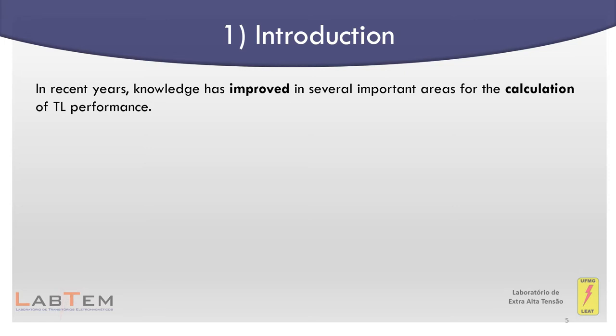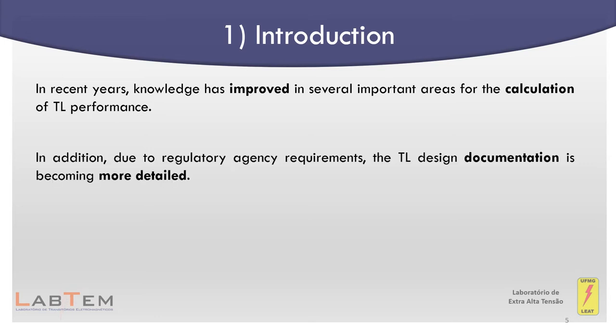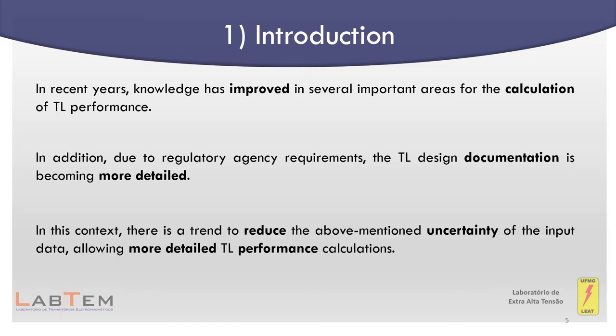In recent years, knowledge has improved in several important areas for the calculation of transmission line performance. For instance, in the characterization of soil and grounding electrodes for impulse currents and in obtaining better estimates for the lightning ground flash density. In addition, due to regulatory agency requirements, the transmission line design documentation has become more detailed. In this context, there is a trend to reduce the above-mentioned uncertainty of the input data, allowing more detailed transmission line performance calculations.